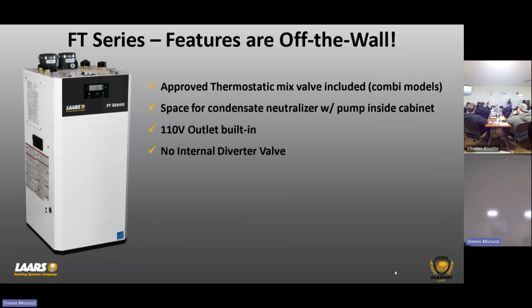Okay. So there's no diverter valve. That diverter valve is a 3-way valve. So I'm in a hydronic heating mode, right? And my wife just turned on the faucet to rinse her coffee cup. What happens? The boiler has to shut off. The diverter valve goes to domestic mode. Now you've got to go through that quick pre-purge and refire the heater, okay?